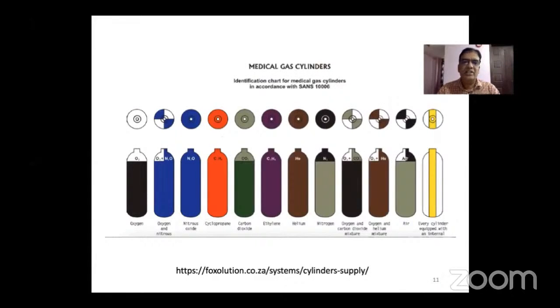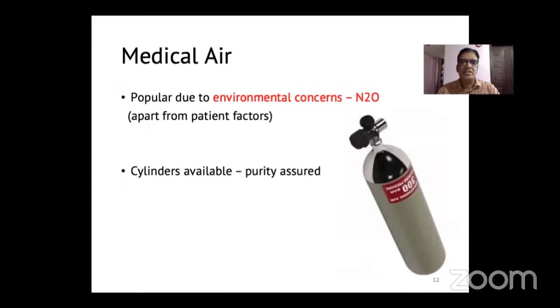So these are the various colors allotted to different gases. Even medical air is obtained through the air only. Basically, it is a more purified form. Cylinders are also available, even though generally they are from the various compressed air generators available in many hospitals. Medical air is popular and gaining popularity because nitrous oxide has certain adverse environmental effects. It has effects on greenhouse gas emissions. And we have indications where nitrous oxide can specifically be replaced with compressed air.